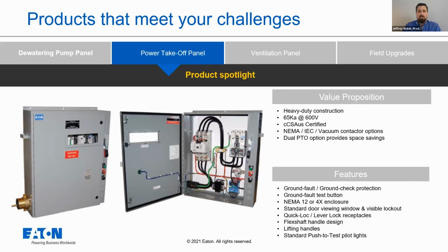Now, sometimes if we talk about a PTO, or power takeoff panel, sometimes referred to as a ground fault panel or even a jumbo panel, which is referring to the load type. The most obvious difference between a pump panel and a PTO panel is the omission of an overload. So the power takeoff panel is used to safely and reliably control electrical power to equipment such as jumbos and bolters at the face.